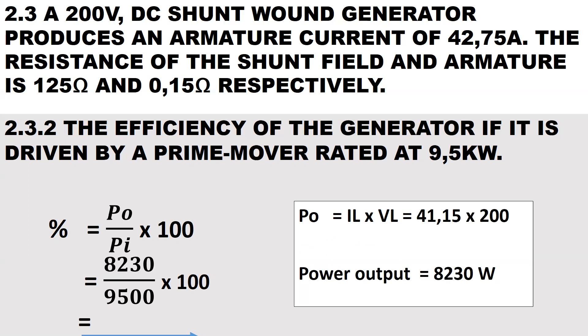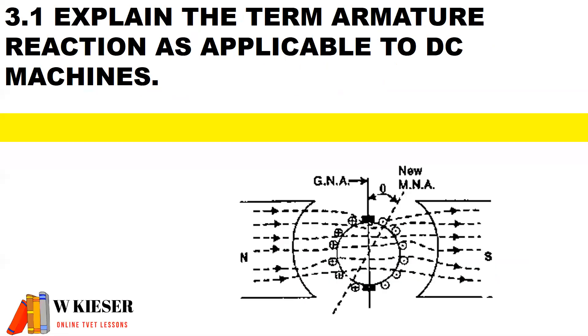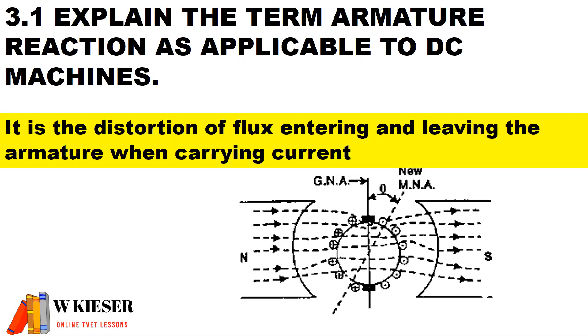To determine the efficiency, it is output power divided by input power multiplied by 100. Therefore this generator is operating at an efficiency of 86.63%. Armature reaction, as applicable to DC machines, is the distortion of flux entering and leaving the armature when the armature conductors carry current. The axis also shifts from the geometric neutral axis to the magnetic neutral axis.